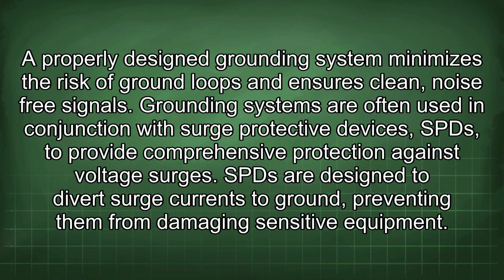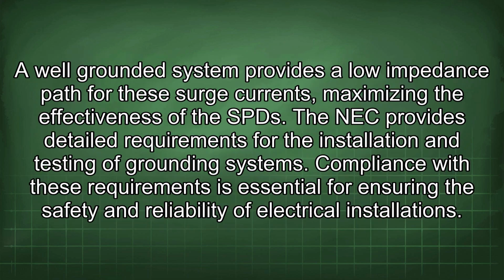Grounding systems are often used in conjunction with surge protective devices, SPDs, to provide comprehensive protection against voltage surges. SPDs are designed to divert surge currents to ground, preventing them from damaging sensitive equipment. A well-grounded system provides a low-impedance path for these surge currents, maximizing the effectiveness of the SPD.